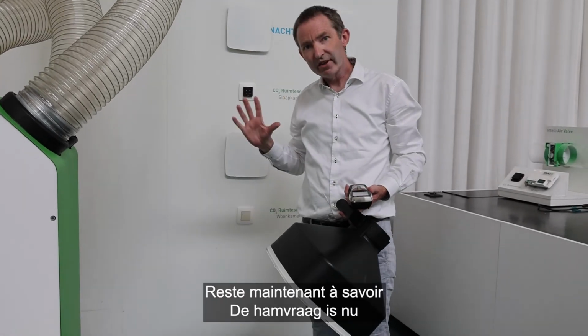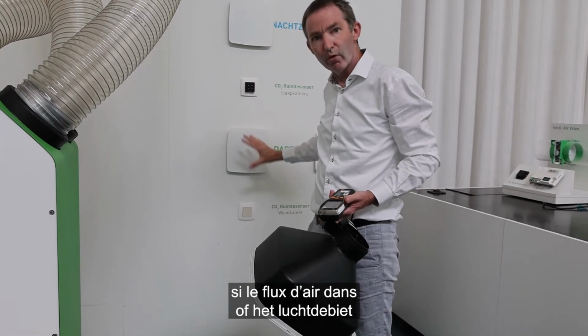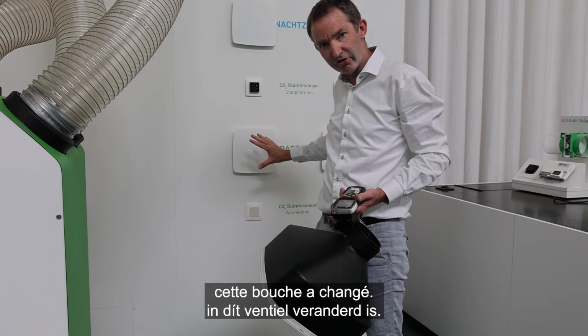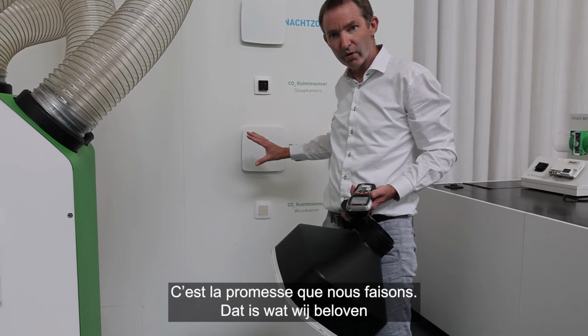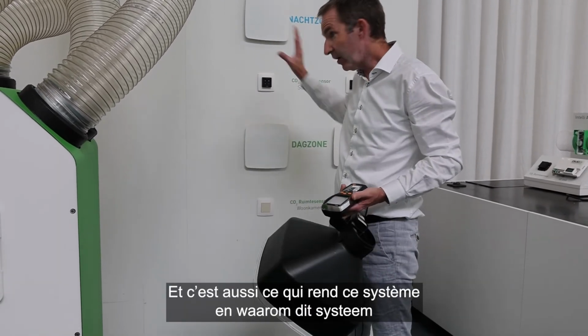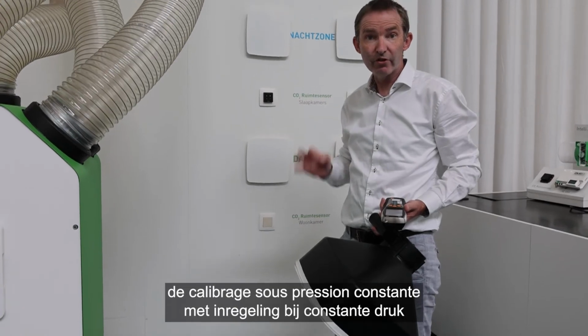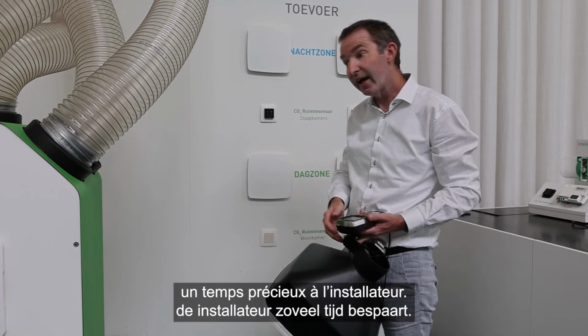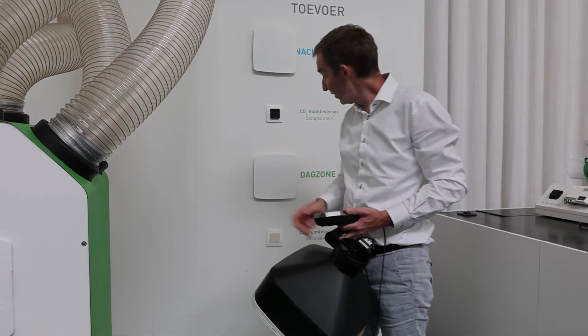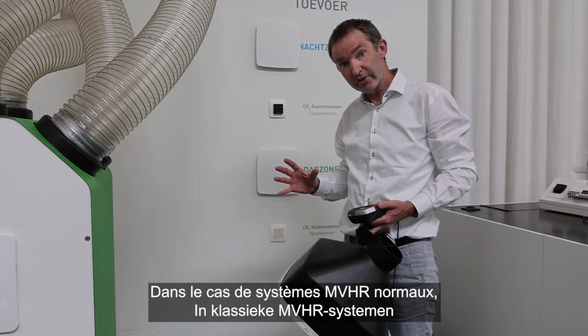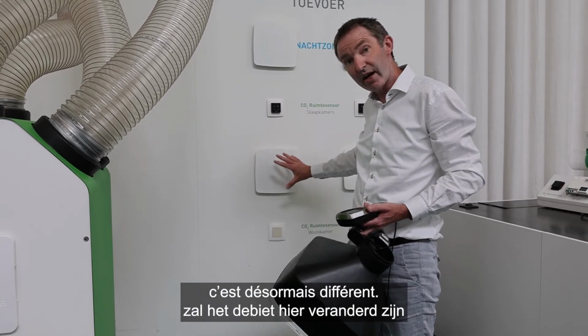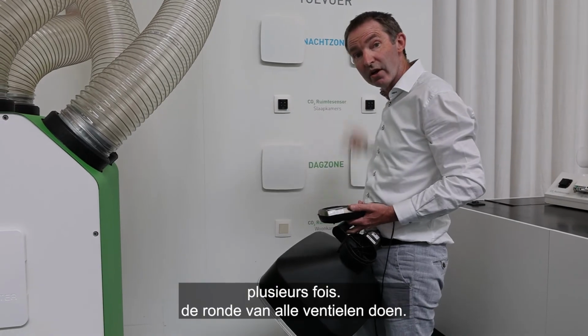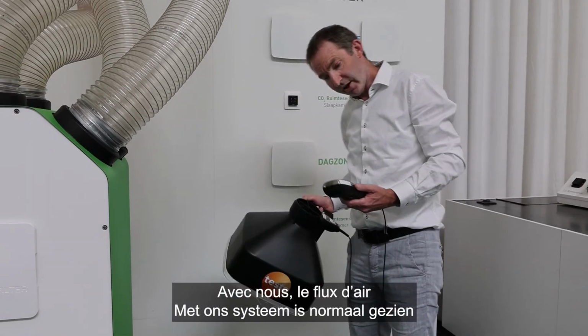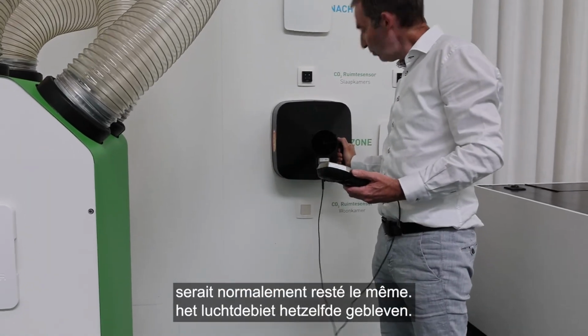The whole magic now is: will the airflow in this vent have changed? Well, the answer is no. This is the promise we make, and this is why this system with calibration under constant pressure is so unique and saves so much time for the installer. In normal MVHR systems, this would now have changed and you'd have to do the tour a couple of times. With us, normally the airflow will have stayed the same.